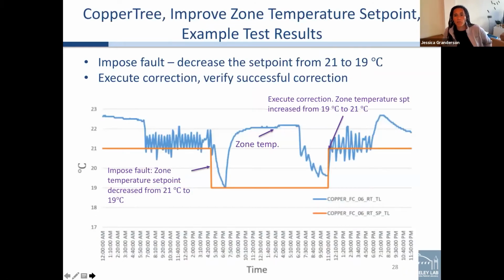The first example I'll give is the correction of zone temperature set points. Admittedly, in the test routine we have to impose the fault, some set point that we don't want active, then trigger the correction routine and make sure it held, that it did what it was supposed to, and didn't cause any unexpected, unintended consequences or ripple effects that would be problematic.